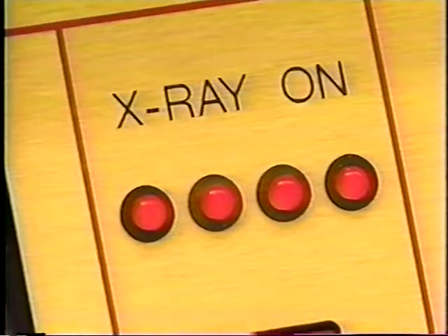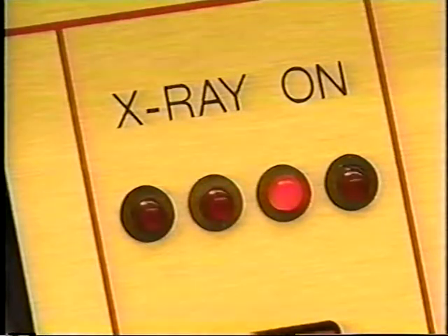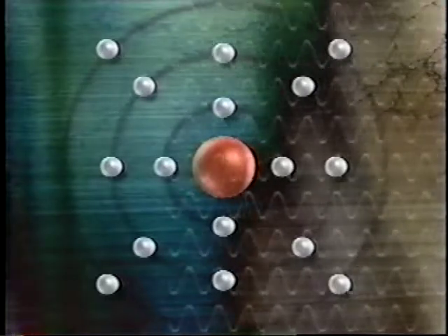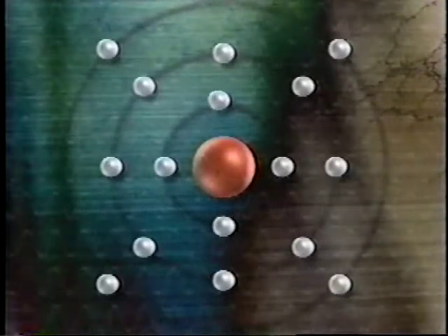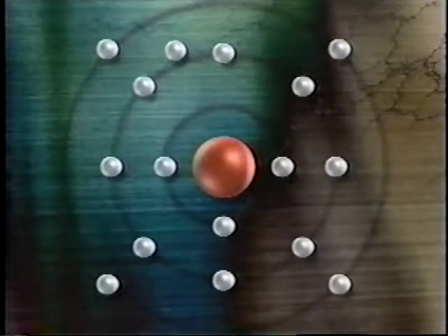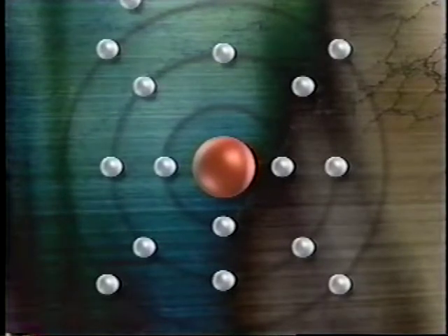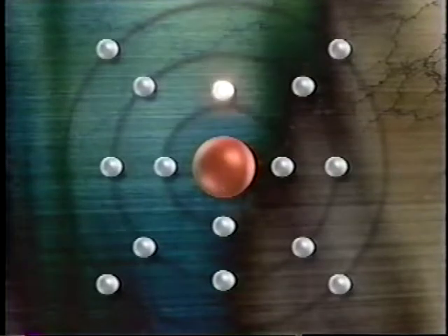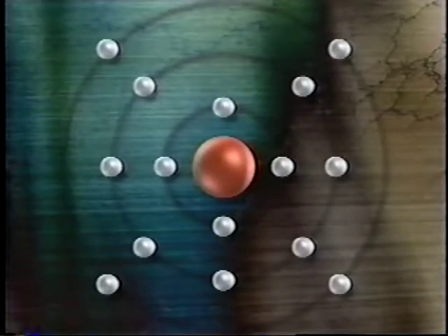In XRF, the sample material collected on a filter is irradiated by high-energy X-rays, which eject inner shell electrons from the atoms of each element in the sample. When a higher energy electron drops into the vacant lower energy orbital, a fluorescent X-ray photon is released.